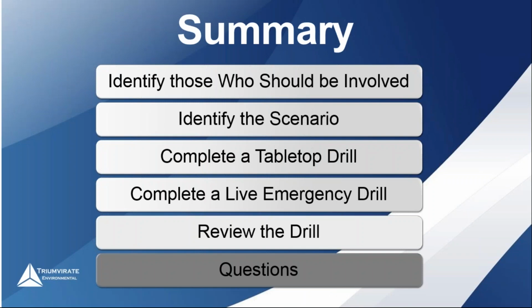So in summary, there are a lot of different scenarios that could always be out there. This particular scenario is one that we've seen with dichloromethane that's gone down the drain. That was actually a particular facility that went through a limestone chip tank. We've seen flammable material that's gone into a wastewater tank. Then we've also seen where a facility didn't have any type of pretreatment system, where flammables went down the drain accidentally and it was going towards a POTW. This type of scenario isn't something that happens all the time, but it does happen out there.